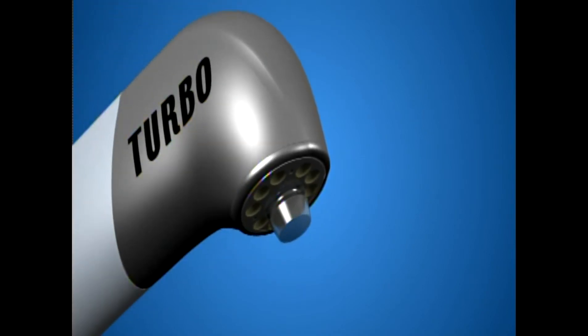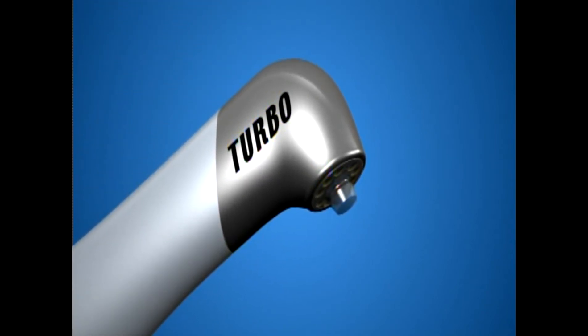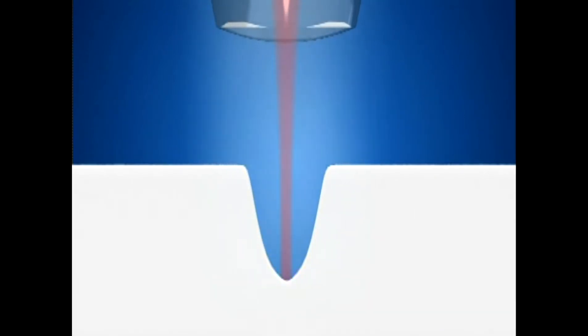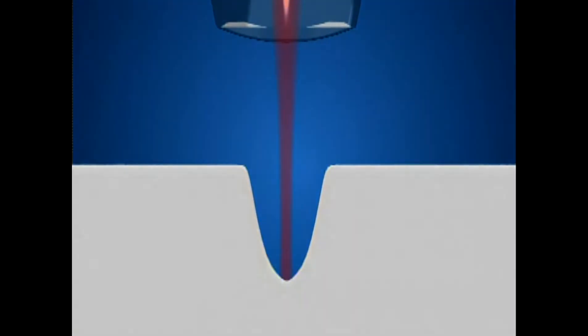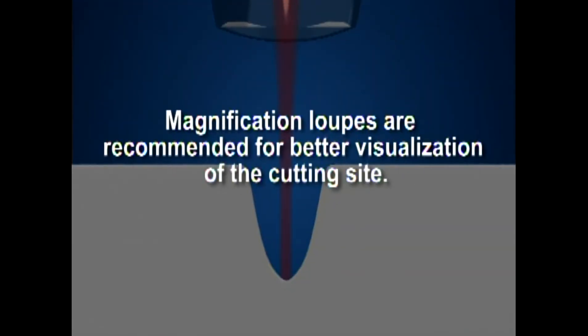The Turbo handpiece is a non-contact handpiece and will require a bit more practice to master the cutting. When speed is needed to cut through hard enamel tooth structure, the Turbo handpiece is your number one choice. The aiming beam will provide guidance to the location of the cutting action. Brief visual checks during preparation are critical since the Turbo handpiece has no tactile feedback. Magnification loupes are recommended for better visualization of the cutting site.